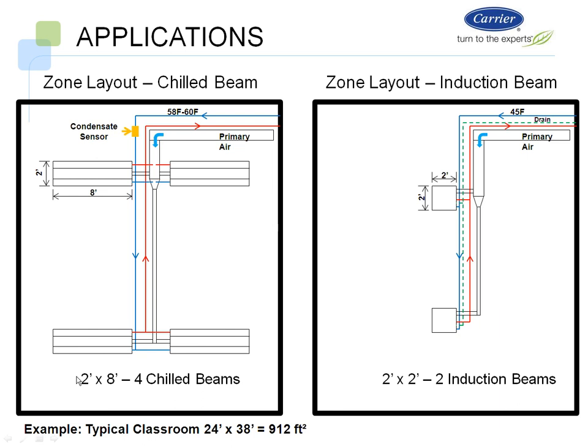Because remember, the air is coming out on both sides on these 2x8s, and then draping across and then coming back and around, and nothing's hitting those sides. So placement is also something you have to be very, very concerned with when you're laying out a traditional chilled beam job. And that's some of the experiences that may happen out there if you don't install those correctly. With an all-way blow, as I said when we had them tested, it was 0.7 of a degree temperature difference, corner to corner, ceiling to floor.